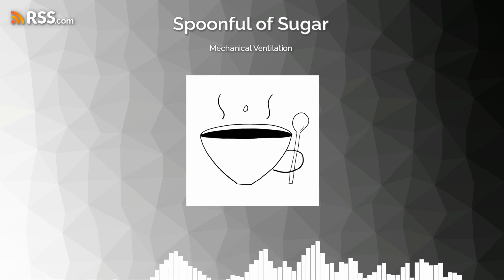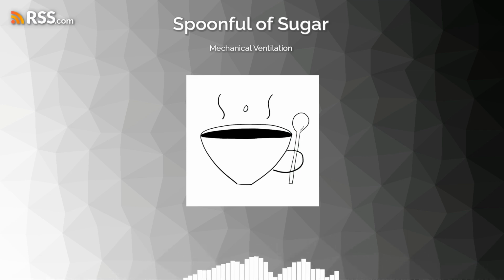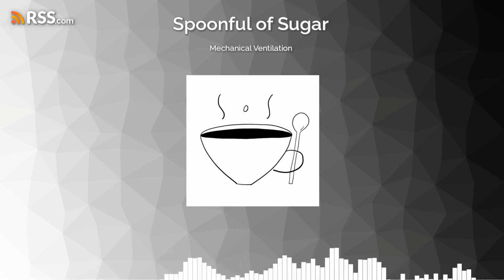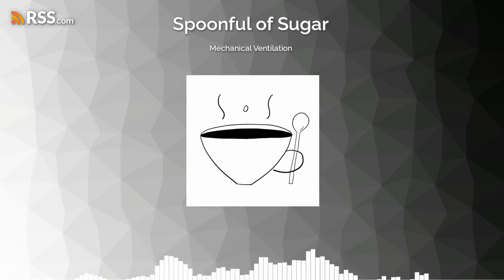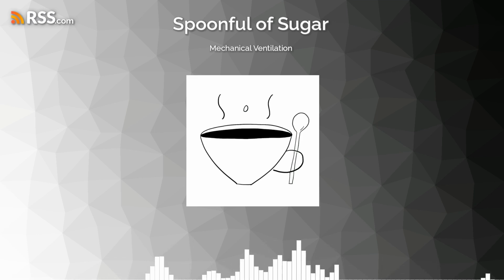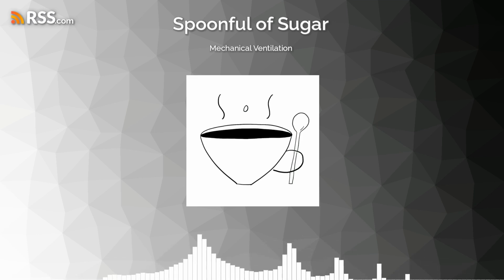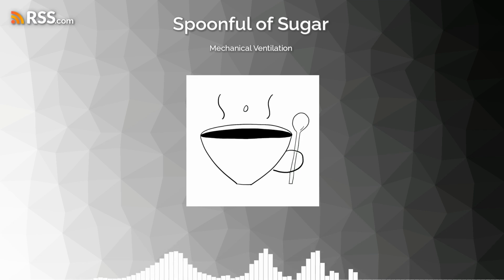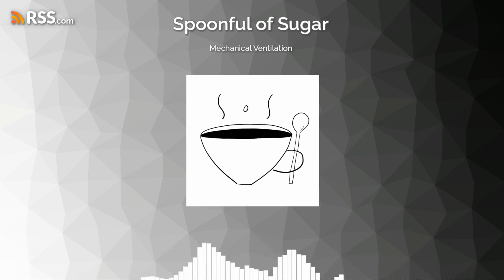Let's start with a tour of the vent. I'll speak broadly to the general setup, but it can be helpful to open up an image and follow along. Every hospital will have different models, but for the purpose of this episode, we'll use the example of a Covidien 980 series ventilator. The first thing I look at on the screen are the numbers at the bottom. These are the settings that you want the patient to do.